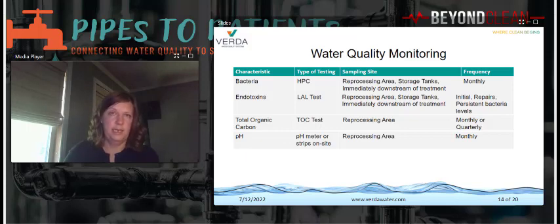Table 6 in AAMI TIR 34 gives an overview of water quality monitoring and the recommended frequency. Monthly testing for bacteria, also referred to as HPC or culture count testing, in the critical water is commonly tested and monitored by facilities. However, how, when, and where are important to ensure the testing is accurate and adequate.